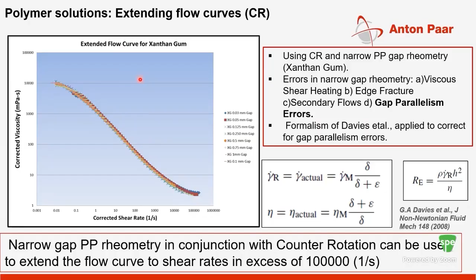So there was no edge fracture. We also computed some Reynolds numbers to ensure that we are below the limit of secondary flows, where secondary flows could actually affect your results. The one thing we had to pay attention to was that once you start going down to very, very small gaps, gap parallelism becomes a big issue, and that can throw the data off. So we used a formalism developed by Davies et al., published in the Journal of Non-Newtonian Fluid Mechanics, where the idea is to do some experiments with a Newtonian oil at different gaps and figure out the error in gap. Once you have that, the results of the final sample, which is xanthan gum in the system, are corrected with that gap error. You can see more details in this paper here. With correction of the data, I could extend the data in excess of 100,000 inverse second. So you can clearly see the benefit of having a counter rotation type device.